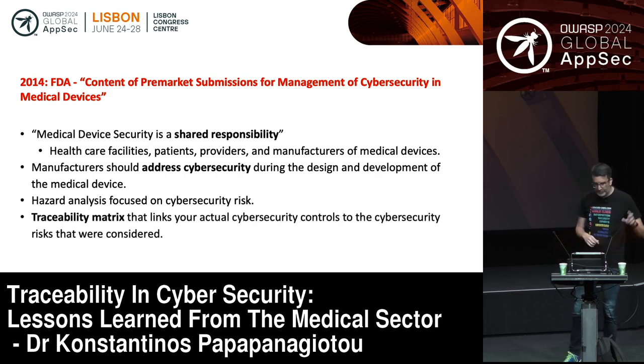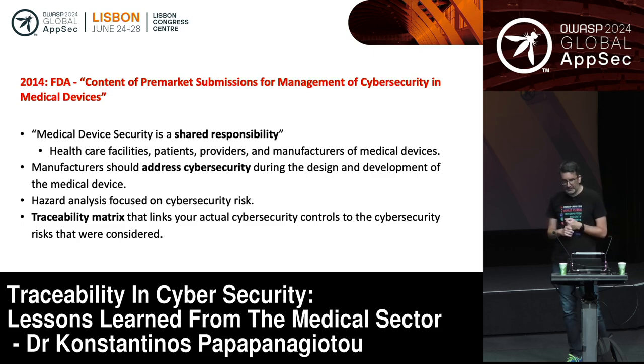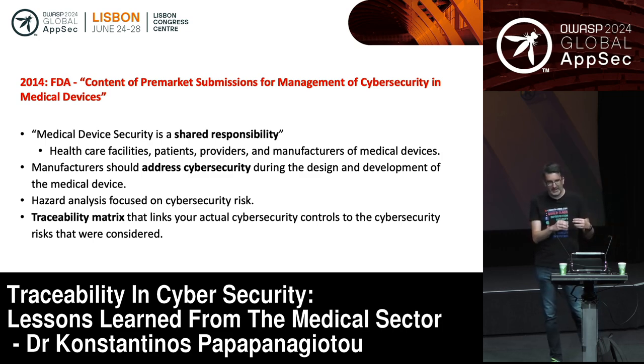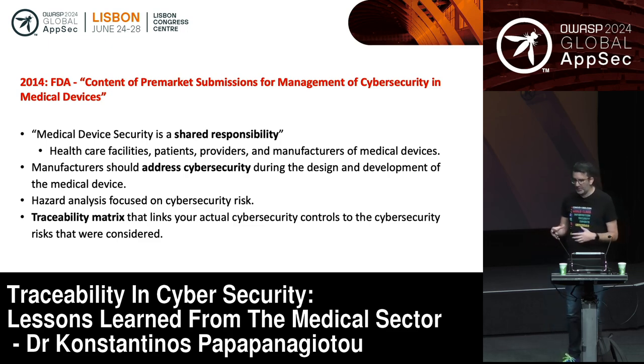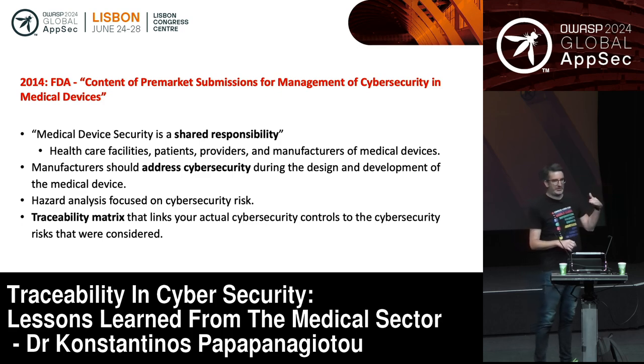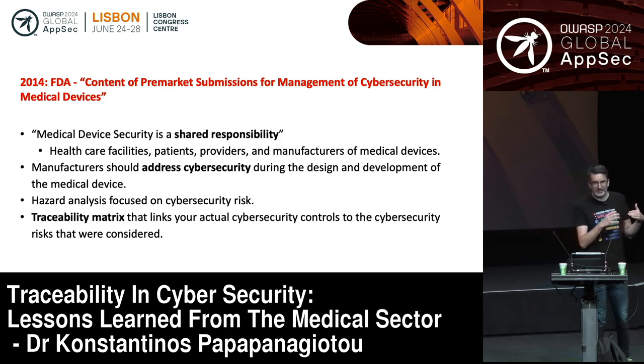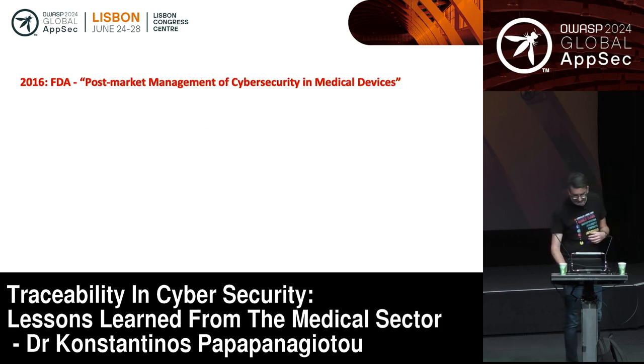And then in 2014, there was an FDA requirement to build a traceability matrix that links cybersecurity controls you decided need to be there with the risks that were considered. So in the traceability matrix, you had to analyze the cybersecurity risks and then explain what kind of security controls you will be implementing to mitigate those risks. And then at the end of the day, you had to test those controls to make sure that they're effectively implemented.